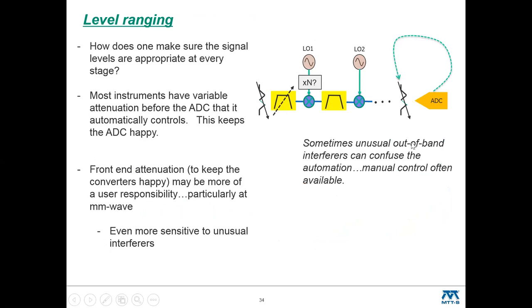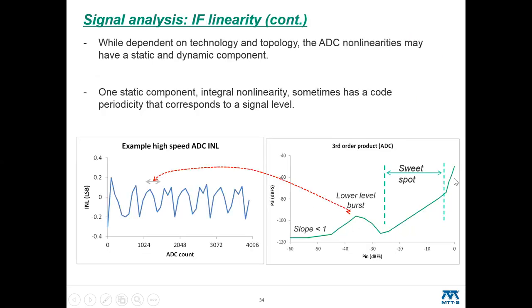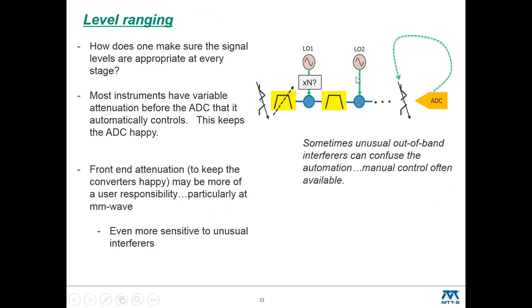Particularly when we talked about variable gain up front before, but there's also often variable gain for the A to D converter, which is, if you're doing your own digitizers, pretty important to understand. In a normal signal analyzer, the instrument takes care of that task for you, making sure the level's appropriate to avoid these problems and things like that. But if you're doing it yourself, you have to pay some attention to it.